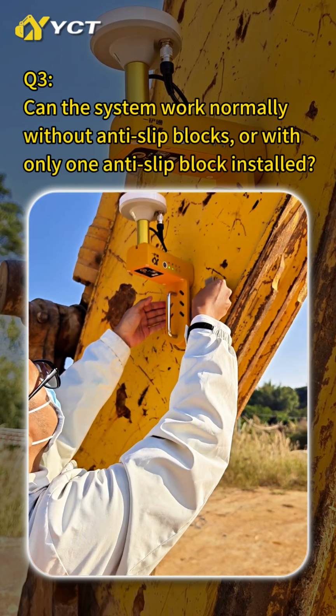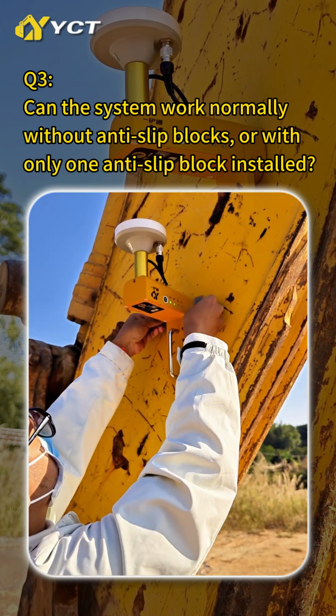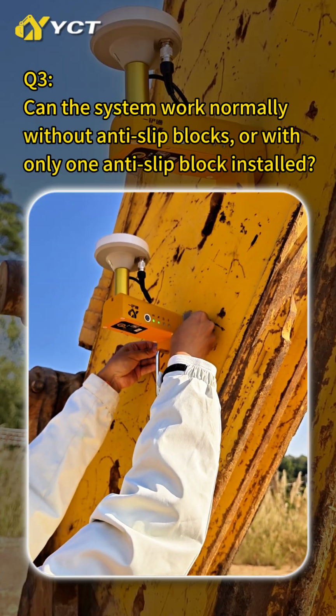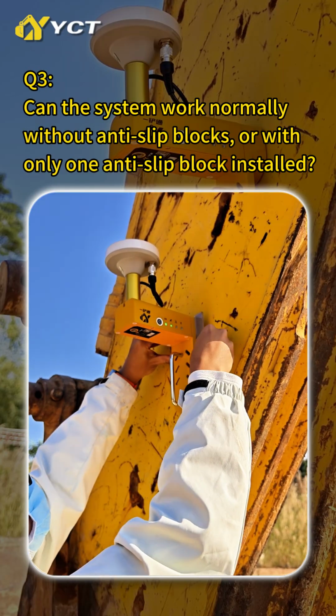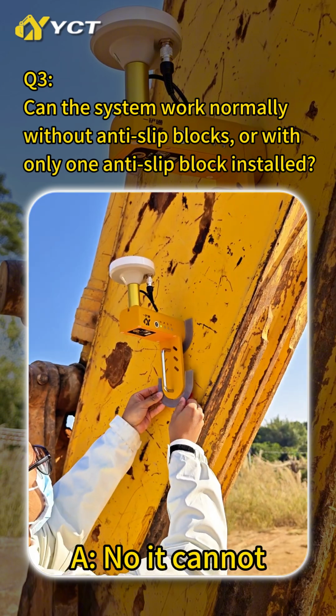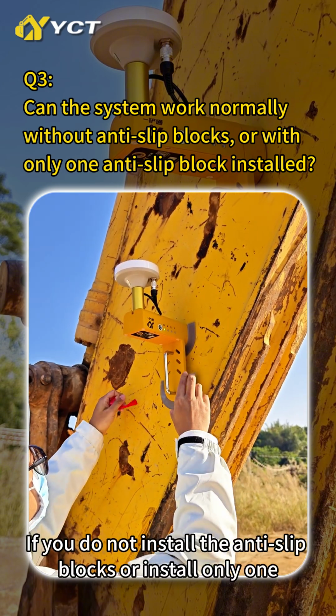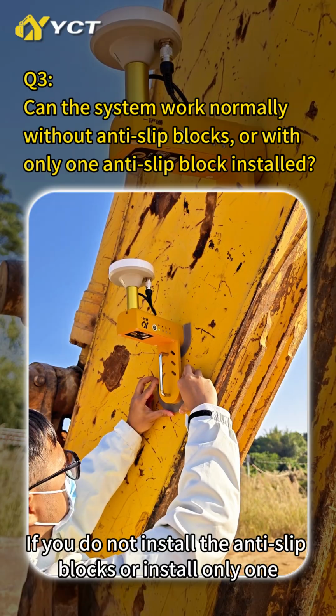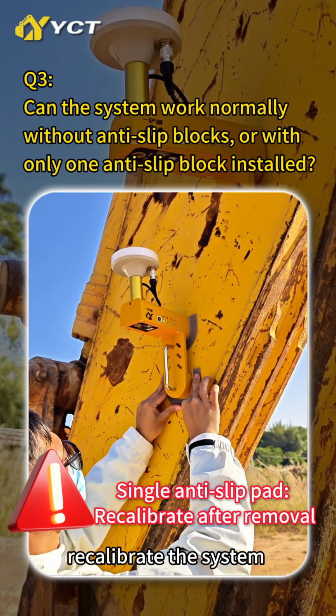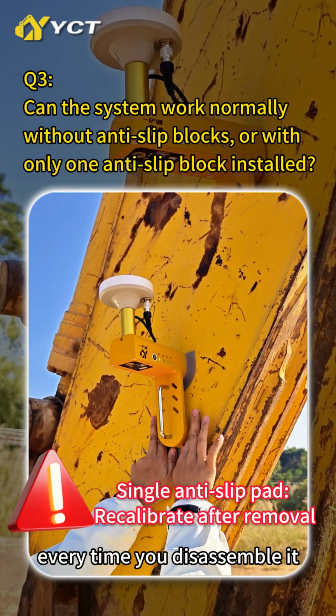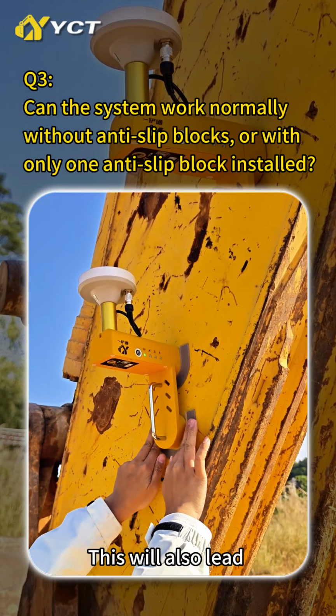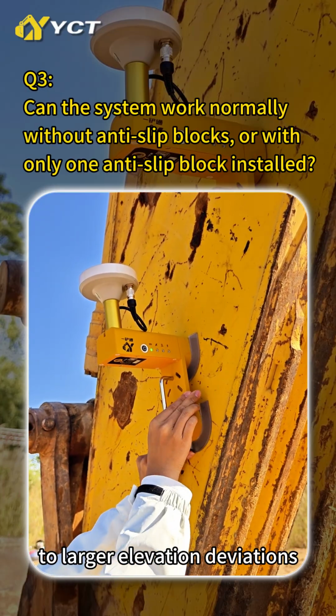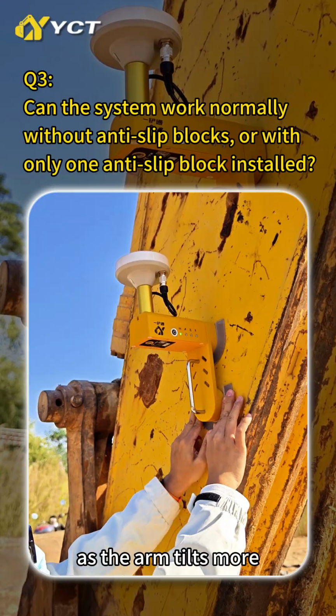Question 3. Can the system work normally without anti-slip blocks or with only one anti-slip block installed? Answer: no, it cannot. If you do not install the anti-slip blocks or install only one, you will have to recalibrate the system every time you disassemble it. This will also lead to larger elevation deviations as the arm tilts more.